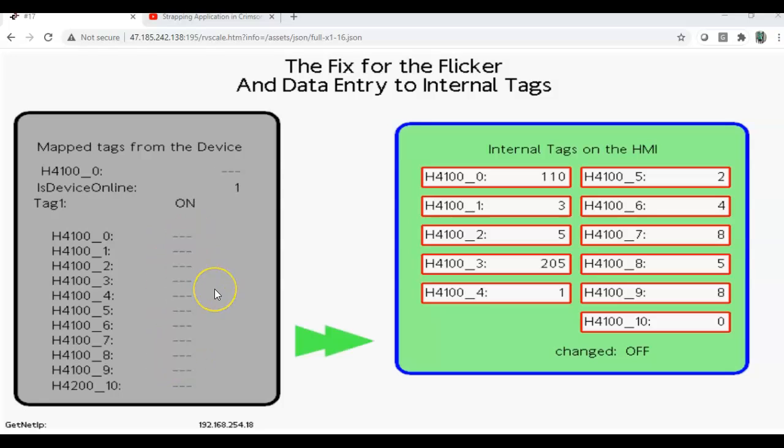And as you see here, they kind of flicker intermittently. Either there's a communication problem, network traffic, it could even sometimes be a tag that's mapped wrong, like this one down here is maybe not mapped right, it never updates. That could be the problem. So anyway, you have a situation like this.